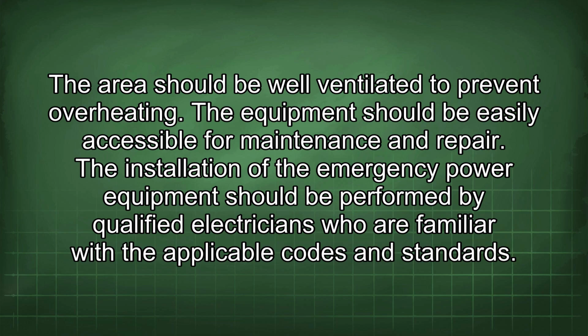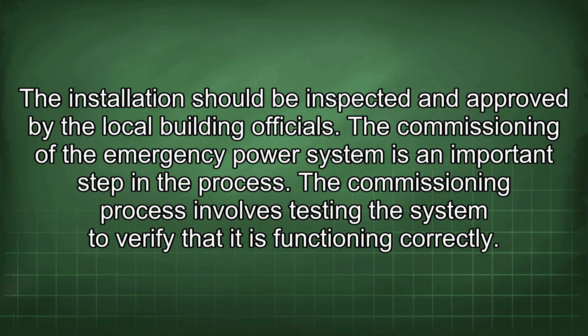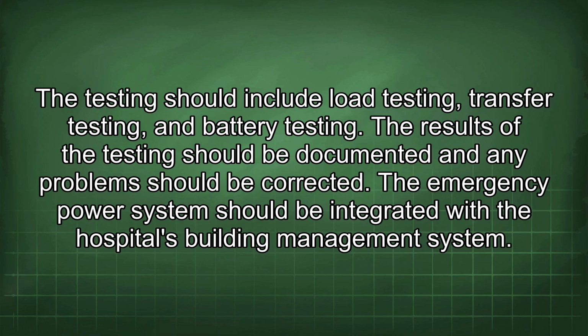The installation of the emergency power equipment should be performed by qualified electricians who are familiar with the applicable codes and standards. The installation should be inspected and approved by the local building officials. The commissioning of the emergency power system is an important step in the process. The commissioning process involves testing the system to verify that it is functioning correctly. The testing should include load testing, transfer testing, and battery testing. The results of the testing should be documented and any problems should be corrected.